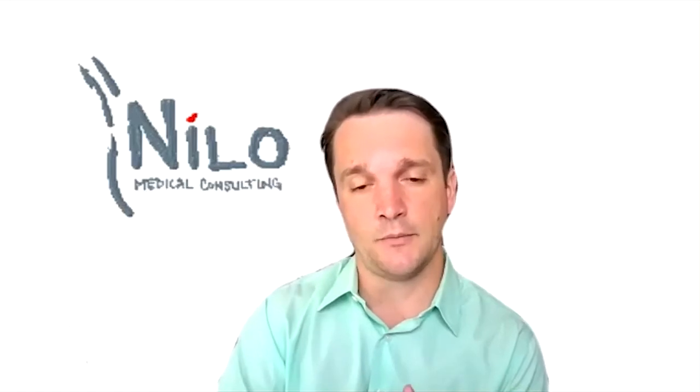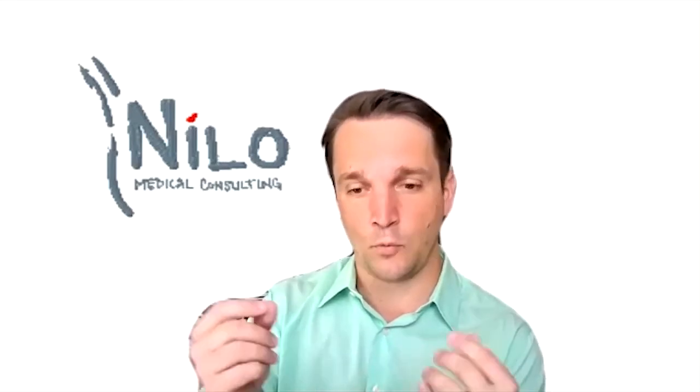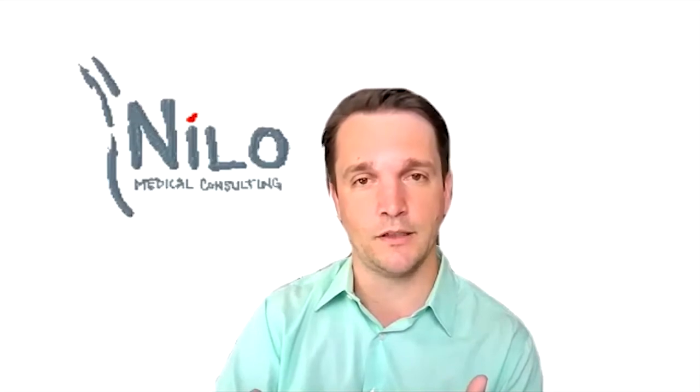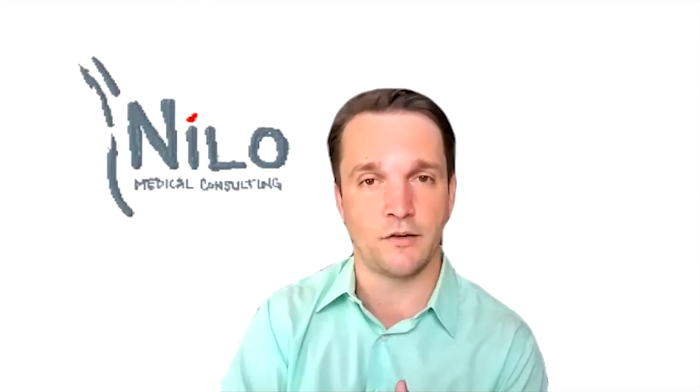Some other things to know early, right when you start, is really define what your user needs are and what the problem you're trying to solve is. Almost all regulation kind of filters down from what's the problem you're trying to solve, what are the user needs, and how have you really set your specifications to meet those user needs. Because medical devices and medical software are so unique to the condition they are treating, there aren't necessarily standardized line for line ways to do this. It is up to the company to define what those requirements are and how you're going to meet them. So that would be, right when you're starting, just make sure you know what problem you're trying to solve, what those user needs are, and design requirements around those user needs.